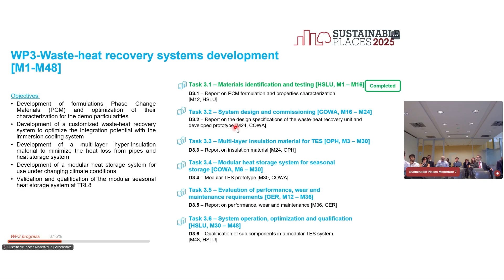We have developed 3 materials within the project, within this target temperature range. We work mainly with salt hydrates because they're cheap, not toxic, and available—basically food grade, so they're also used in many food industries. We settled on 3 materials, focusing mainly on PCM 58, at a phase change temperature of 58 degrees C, and PCM 45, which we've now tested over 1,000 cycles in the testing unit I'll show after. In the end, we selected PCM 45 for our first prototype because its phase change temperature is just low enough to be charged by a server unit—there's always a trade-off, since increasing the temperature in the immersion cooling unit makes the servers run less efficiently, but we still need to be able to charge the phase change material.